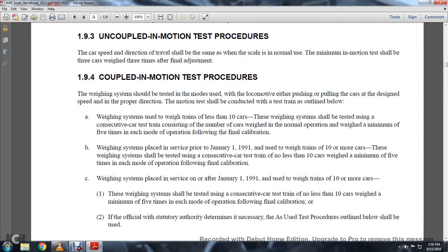The weighing system placed in service prior to January 1st, 1991, used weight trains of 10 or more cars. The weighing system shall be tested with the consecutive car train of not less than 10 cars, weighed a minimum of five times each mode of operation following final calibration.